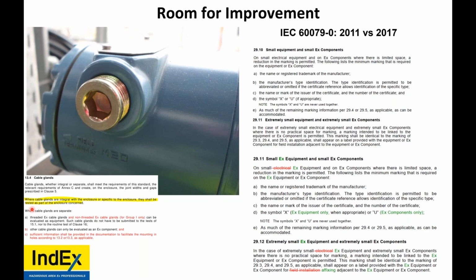Now, even for Ex d, where cable glands are an integral part of the enclosure or specified for the enclosure, those shall be tested as part of the enclosure concerned. So if it's part of it, it doesn't necessarily have to be marked itself. This plug doesn't necessarily have to be marked, but they have to make reference to it on the marking of the equipment. They didn't do it in this instance. The easiest way would be to just mark the plug.